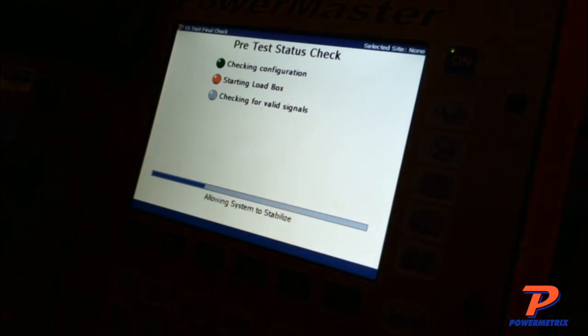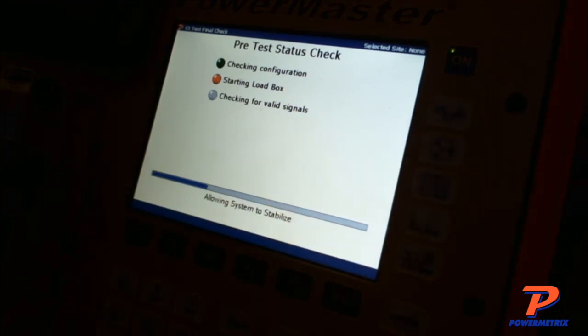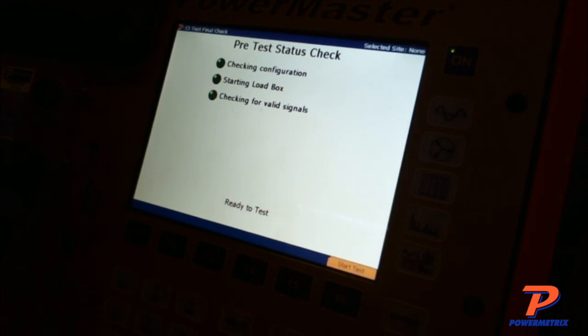I guess I should bring this up too. This happened to me at a utility company. When you're doing a benchtop test for one of these CTs, I can test 25 kV, 15 kV, large high voltage CTs on a benchtop test. Think about that for a minute. That's because I'm just driving a primary current through there and reading a secondary current. I'm not connected into the system, so I couldn't smoke or damage any equipment by being at too high a voltage. I can do that. I've done it before.